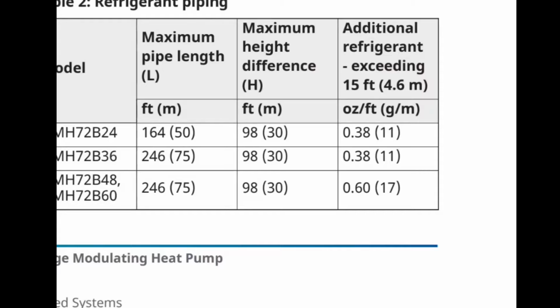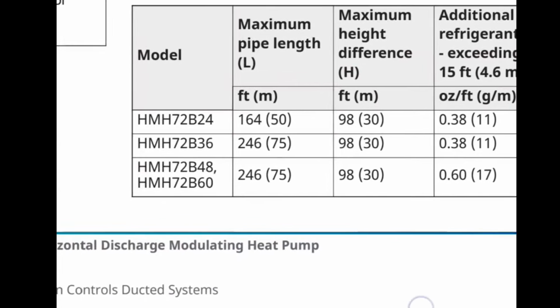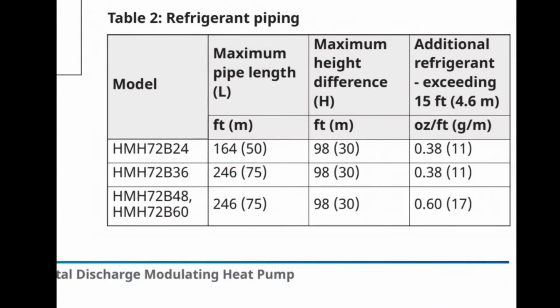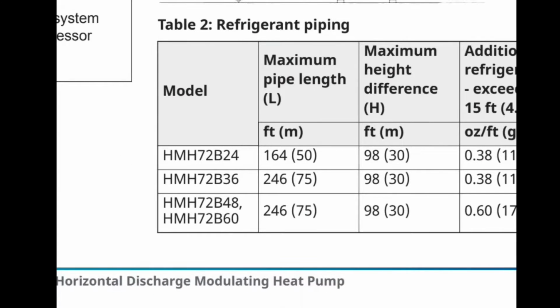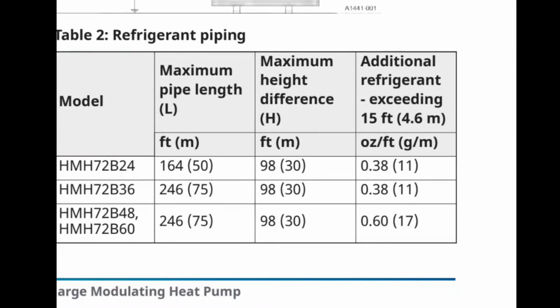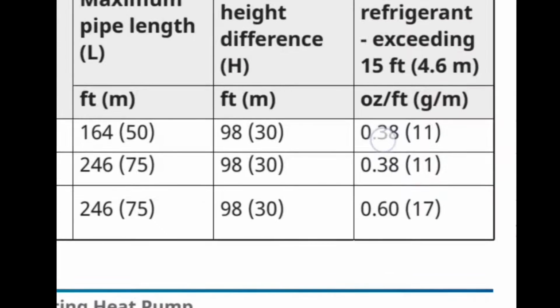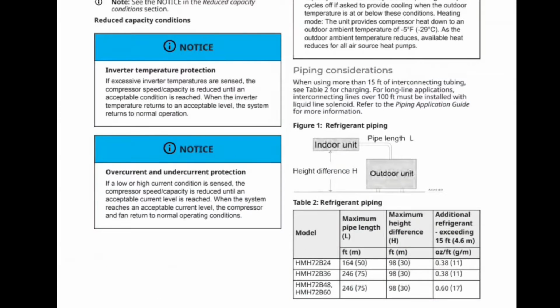So additional refrigerant exceeding 15 foot. I've got 80 foot, so that remaining 65 foot that I have, I'm going to times that by 0.60. And that's going to give me how many ounces I need to charge additionally. I think it's amazing that the HMH7 can have a total maximum pipe length of 246 feet. You see that? And then maximum height difference is 98 feet. All right, let's charge it up.